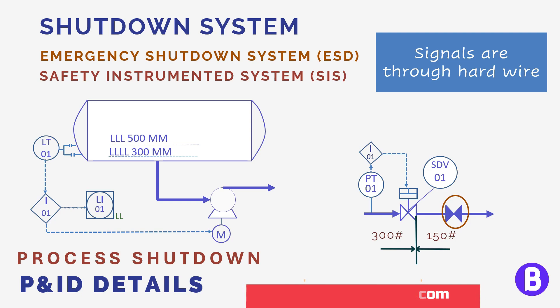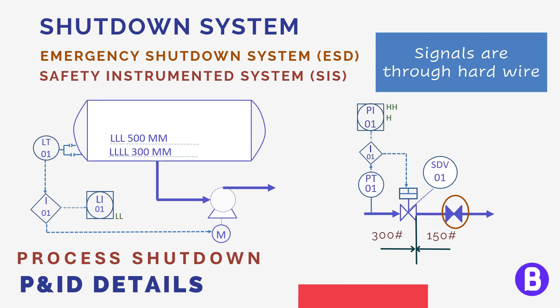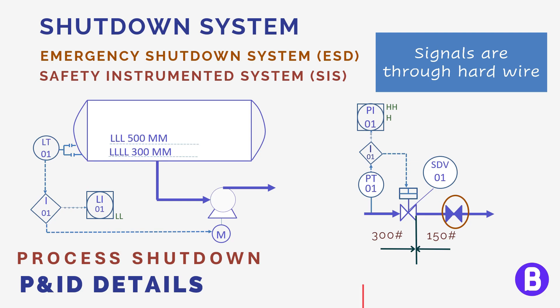Here the pressure transmitter shall send a signal through hardwire to the shutdown system, and through interlock logic, if the reading of the pressure reaches the shutdown pressure — which is the high-high pressure here — a signal shall be sent to close the shutdown valve. Now the low pressure system won't be subject to overpressure, as the shutdown valve is closed and there is no flow from the high pressure system to the low pressure system.